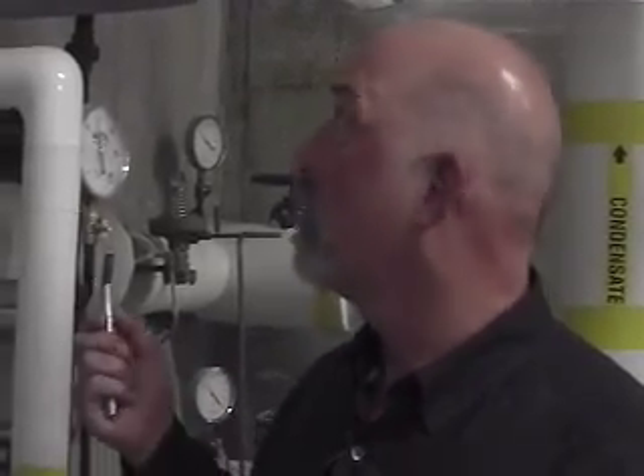Yeah, you want to make sure that on installation, some of that stuff should have been taken apart, and if it wasn't, it should have been. But you want to make sure when you operate these PRVs that you don't operate them too close to the set pressure, because that valve will sit in there and chatter, wear out. So it looks like it's set pretty good right now.